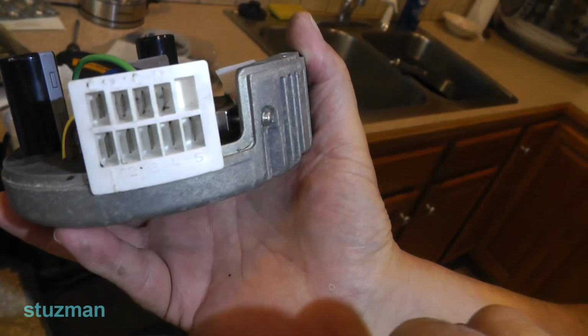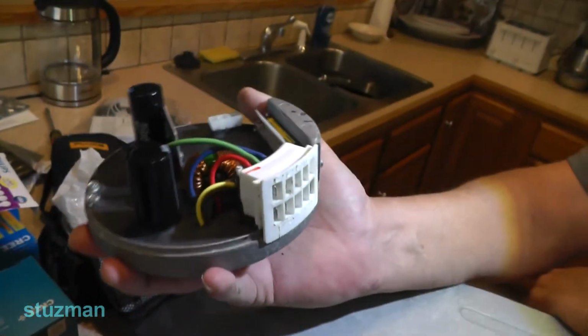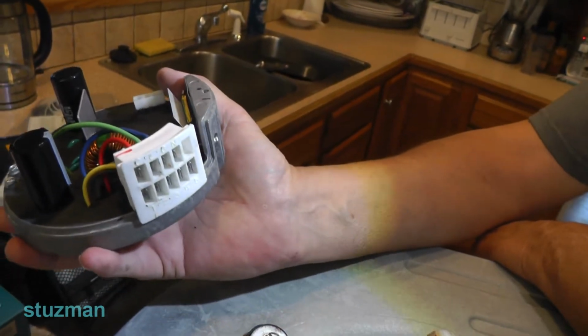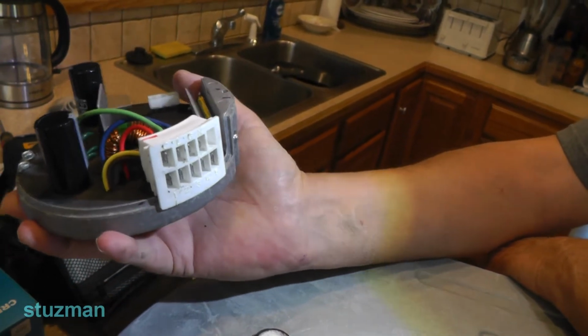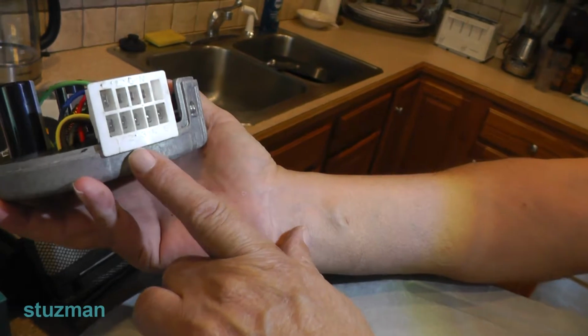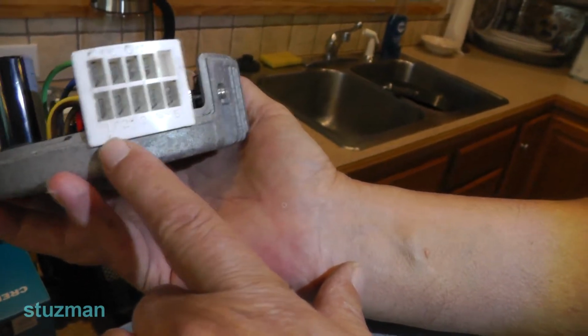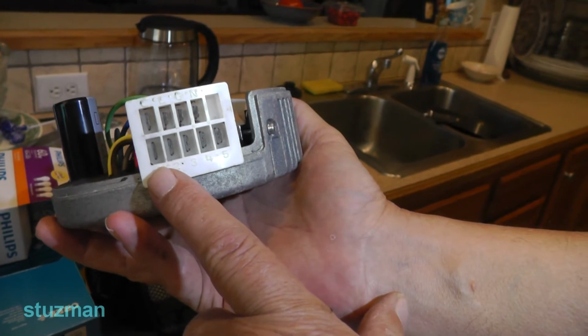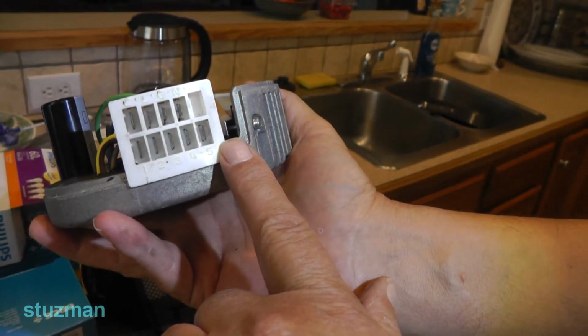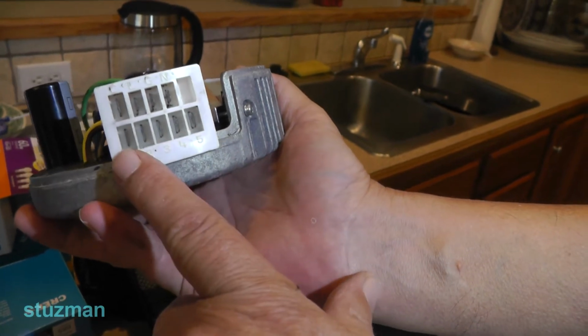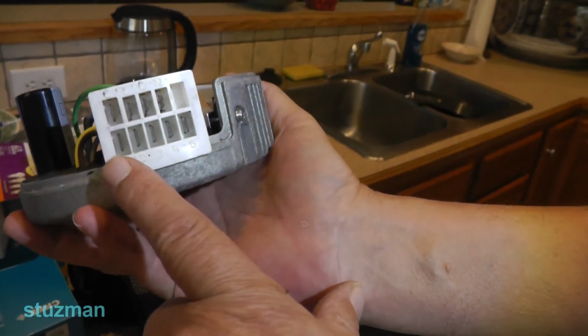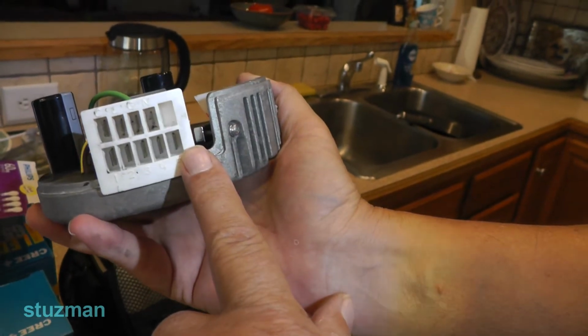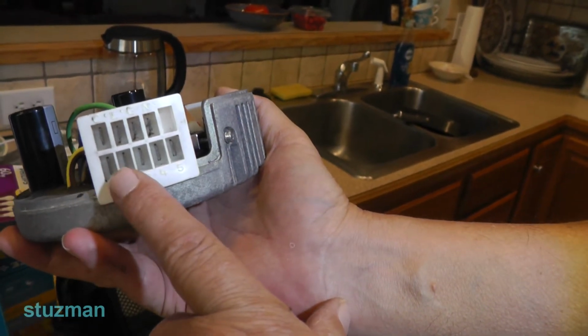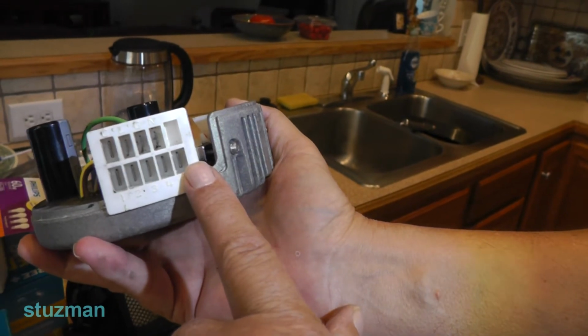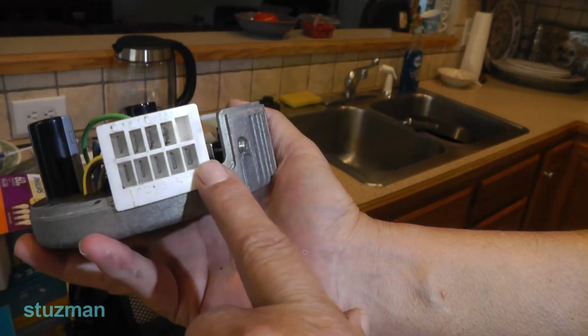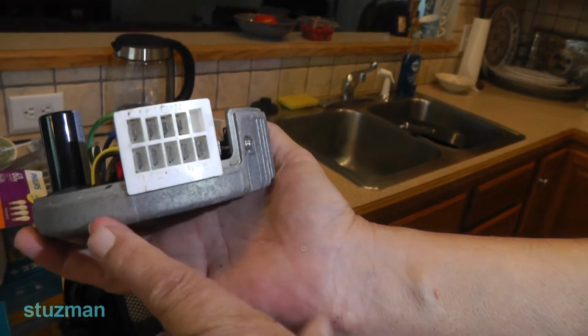Okay. So when you buy these units, you can't get a generic replacement because there is no standard among manufacturers that, say, if it's single stage for heat, it's going to be on number 1. It's left up to the manufacturer. They can program any terminal they want for whatever torque setting they want. Now, a lot of times people will say these are speed taps, but they're constant torque. This is a constant torque motor. So the variations between these taps will give you various torque settings, and then that will actually vary the speed too.